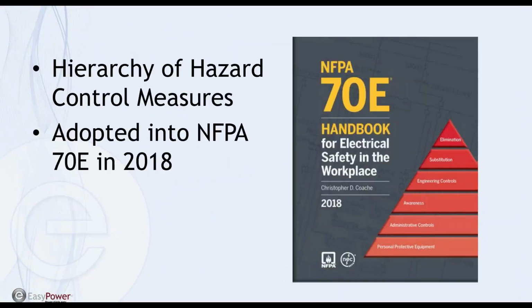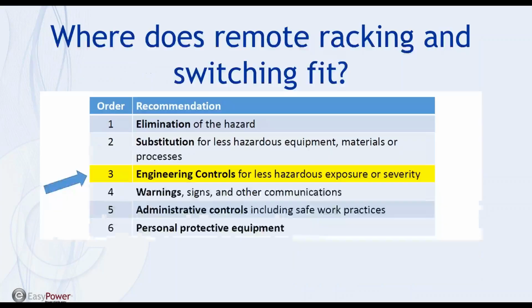So in 2018, NFPA 70E introduced the hierarchy of hazard control measures and adopted it into 70E. And the reason I point that out is I like to showcase where our type of solutions, that's remote racking and remote switching, fit in that hierarchy. Number one, the best thing you can do is eliminate the hazard, which by far is the absolute best solution, and then the least effective form of protection is wearing PPE. Then it makes a case for remote switching and remote racking. It falls in as item number 3, an engineered control for less hazardous exposure or severity.